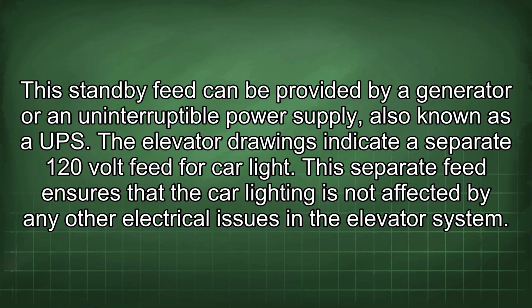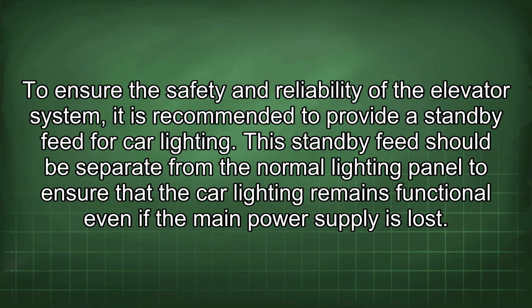The elevator drawings indicate a separate 120-volt feed for car light. This separate feed ensures that the car lighting is not affected by any other electrical issues in the elevator system. To ensure the safety and reliability of the elevator system, it is recommended to provide a standby feed for car lighting. This standby feed should be separate from the normal lighting panel to ensure that the car lighting remains functional even if the main power supply is lost.